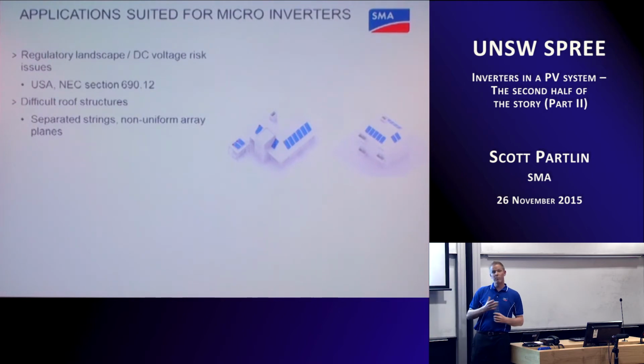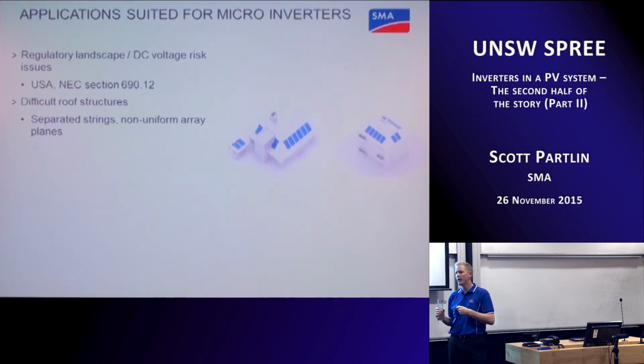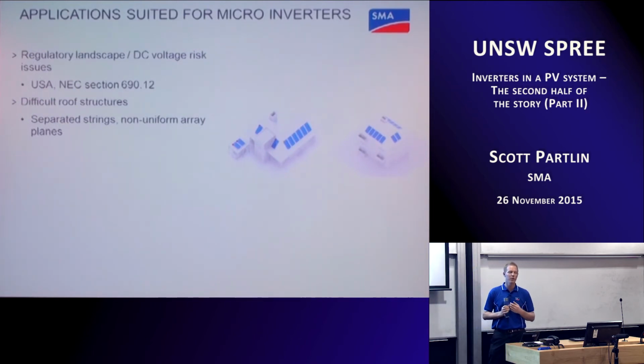Difficult roof structures are also an application where microinverters are much better suited. Because of their modular nature, you can just put one here and one there and another one there. They don't need to have their DC connected. They don't need to be installed in the same plane. They can be separated across the roof. That makes them a lot more suitable than, say, a string inverter, because there's no need for protection of DC cabling runs. Also, for example, you can see here on some of the roofs I've tried to show, there's all these different orientations, and you will all well know that the output power of a PV module is a direct relationship to the input sunlight, and the input sunlight to each of those arrays is different. So trying to design a system where all of those modules were connected would be very, very challenging to get right and to actually make sense. So a perfect application for something like a microinverter.